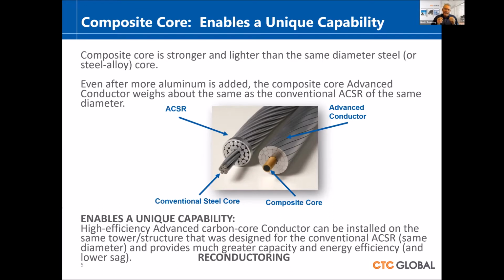It's so much lighter that even after you add more aluminum, and you can see here on the right is the trapezoid, aluminum is filling up all the holes. There's about 28% void when you use those round wires in an ACSR. When you fill those up, you got about 28% more aluminum. And the advanced conductors also use a more conductive annealed aluminum as well. So even after you add the aluminum, it turns out it's the same weight as the ACSR.